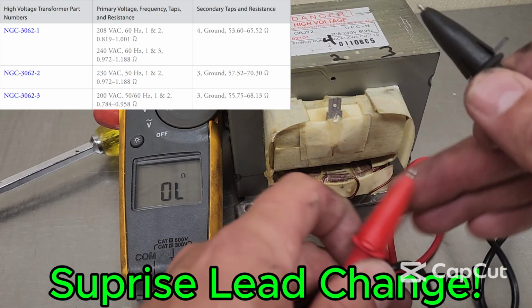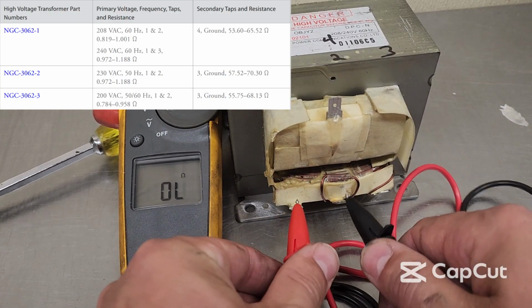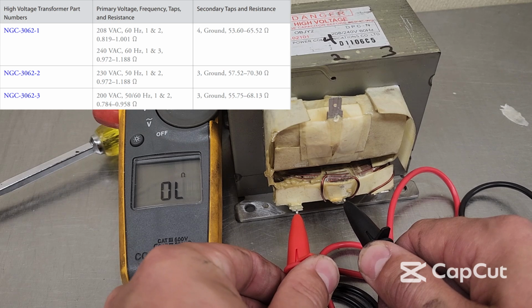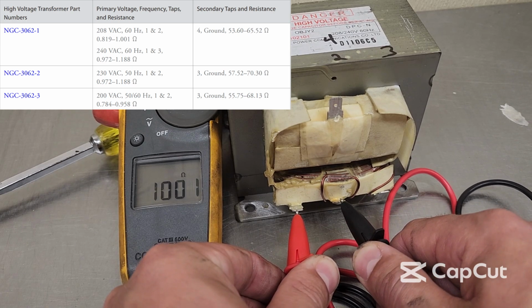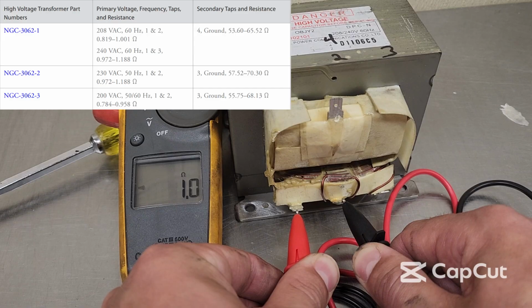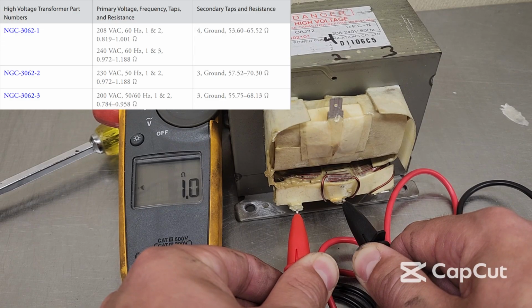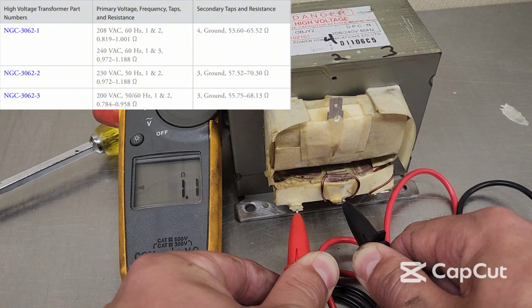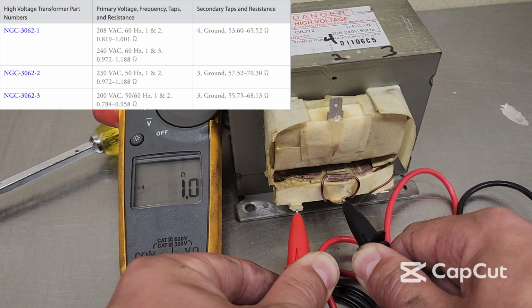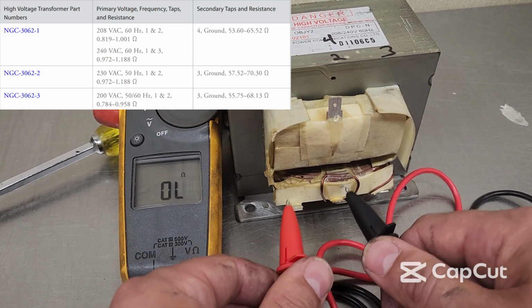On this particular transformer, in this particular configuration for this US model oven, you're looking 1 to 2 is your 208 volt, and you're looking for 0.819 to 1.001 ohms. In this case, we don't have quite the value reading to show that, but these leads give 0.1 ohm, so we remove 0.1 ohm from this value, and we are right where we need to be in the value of this transformer. So that's your 208 volt tap.